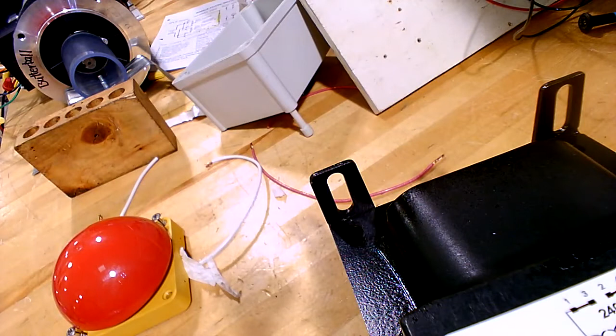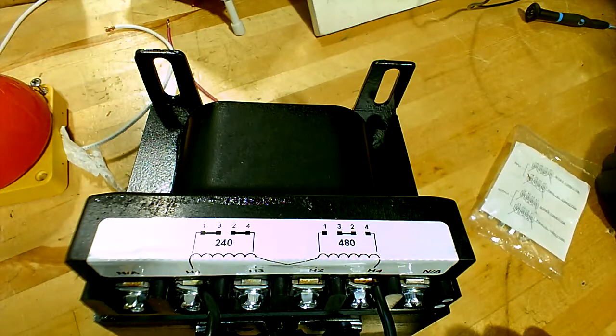So anyway, as far as these jumpers, they come in a bag like that. There's two of them. You have to decide whether you're going to wire for low or high voltage, series or parallel, coming in. So when you measure, you get your value there. If you've got 240 coming in, we're in the range of 240. We have 208 still in this connection. If it was going to be 480, we're going to use this connection. If you have 480 coming in to the machine, you use this one, low or high. And your jumpers will go accordingly.